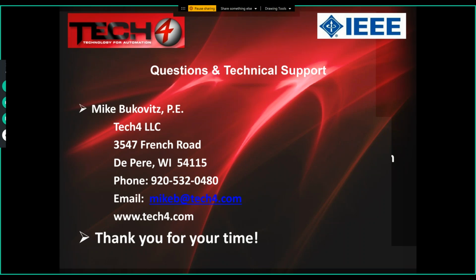We now go to the secondary gear. And again, if you have a best practice design, you have a device like a Panduit VeriSafe. Now, a Panduit VeriSafe device per NFPA 70E replaces the need for a digital multimeter absence of voltage test because it's a positive voltage test device. It tests both phase to phase and phase to ground and tests the tester itself. So in literally less than a minute, I've locked out, tagged out, and put my substation in an electrically safe working condition. Go to work. That's exactly how it works.